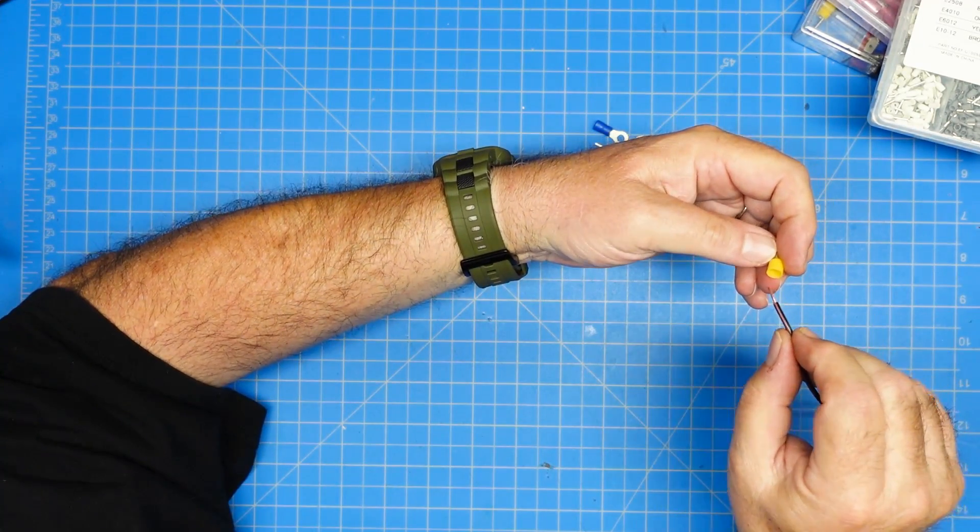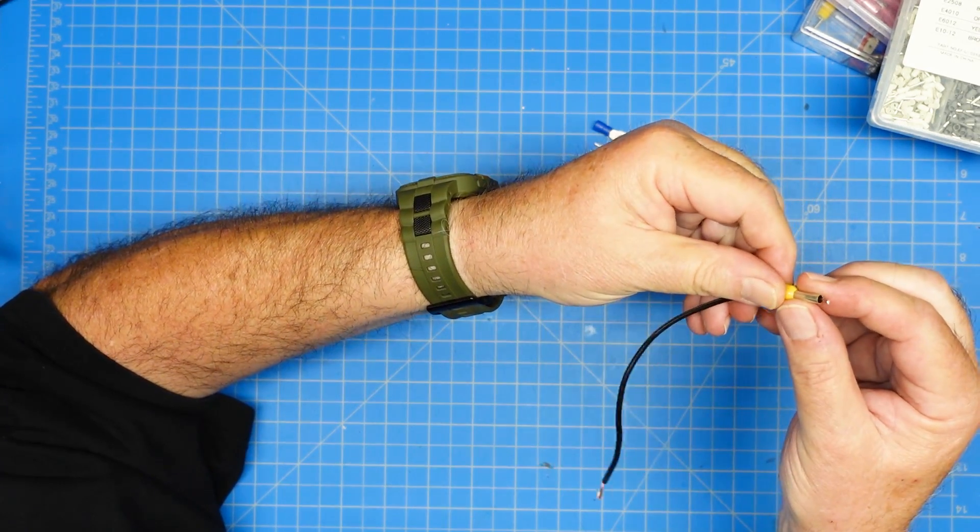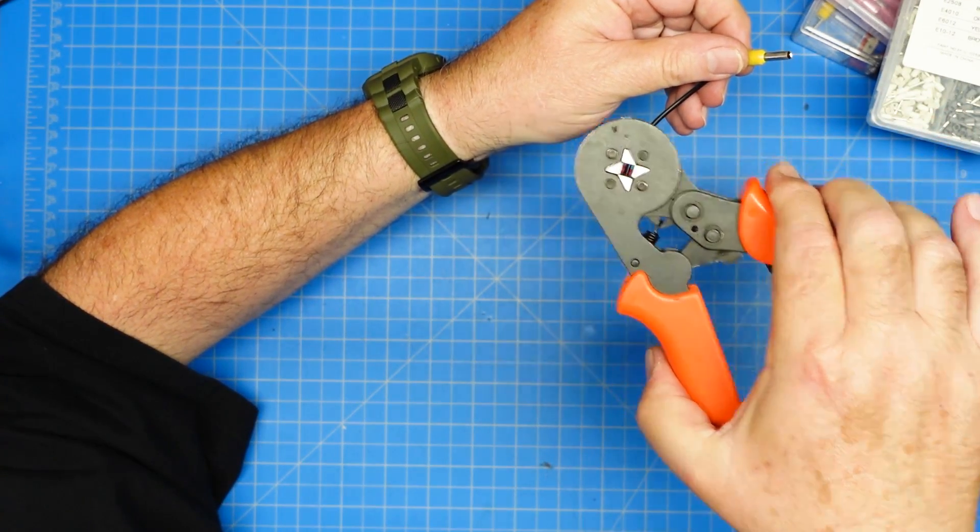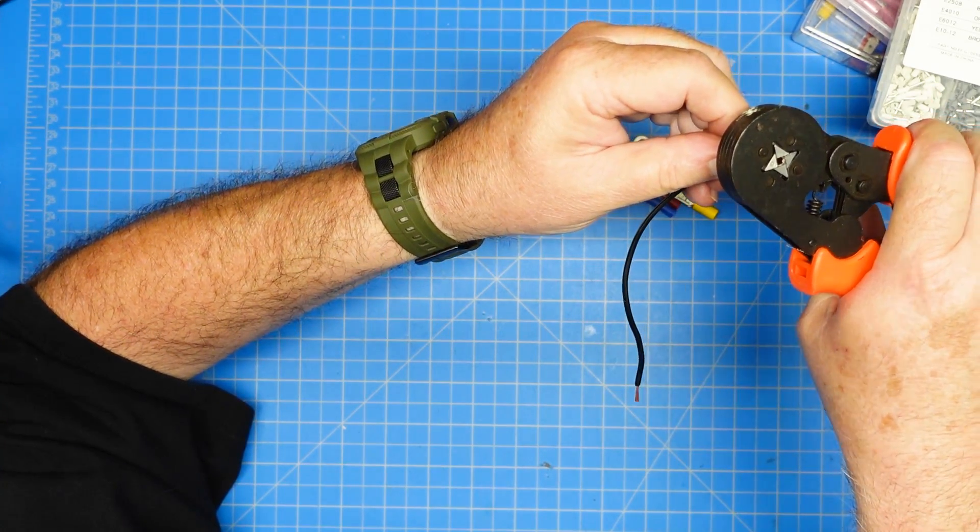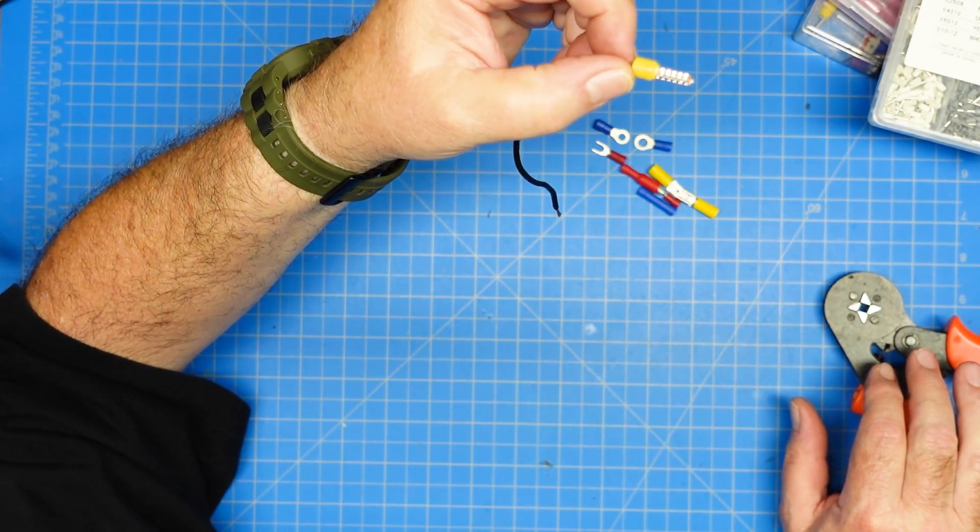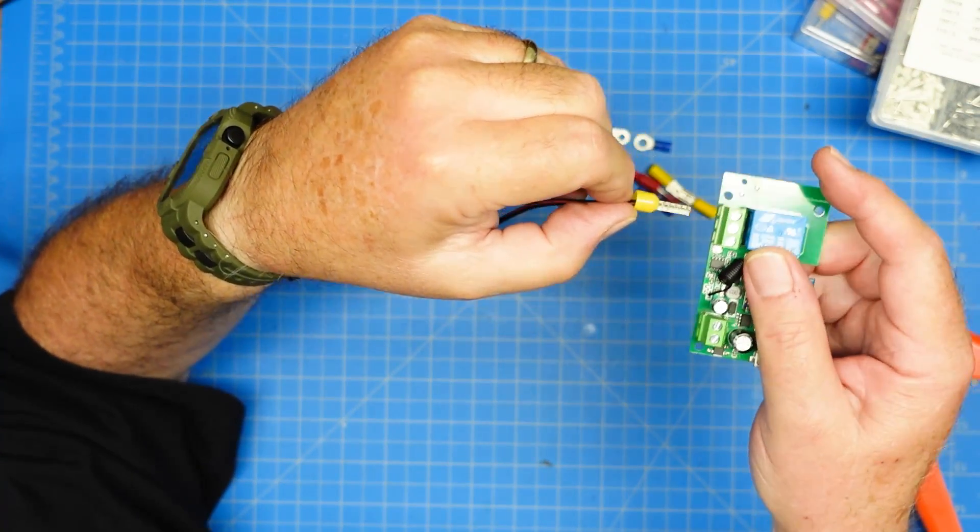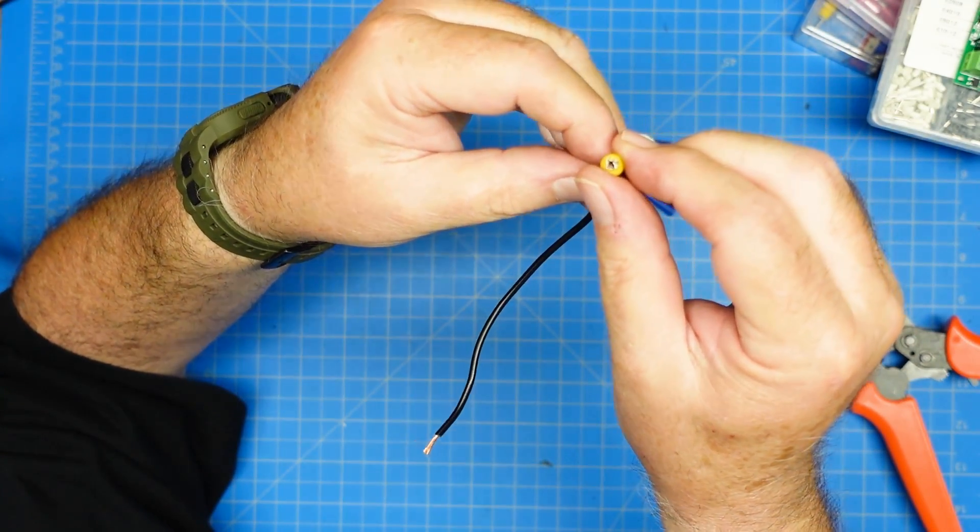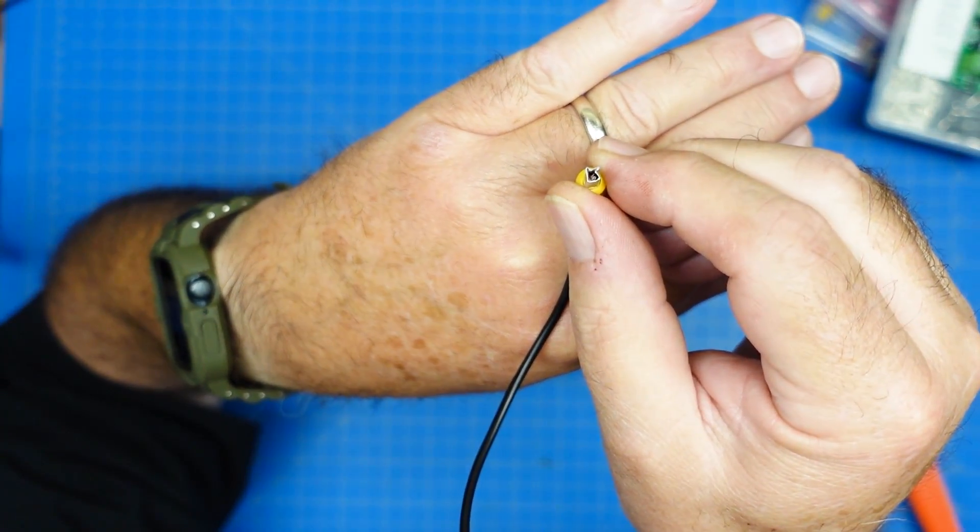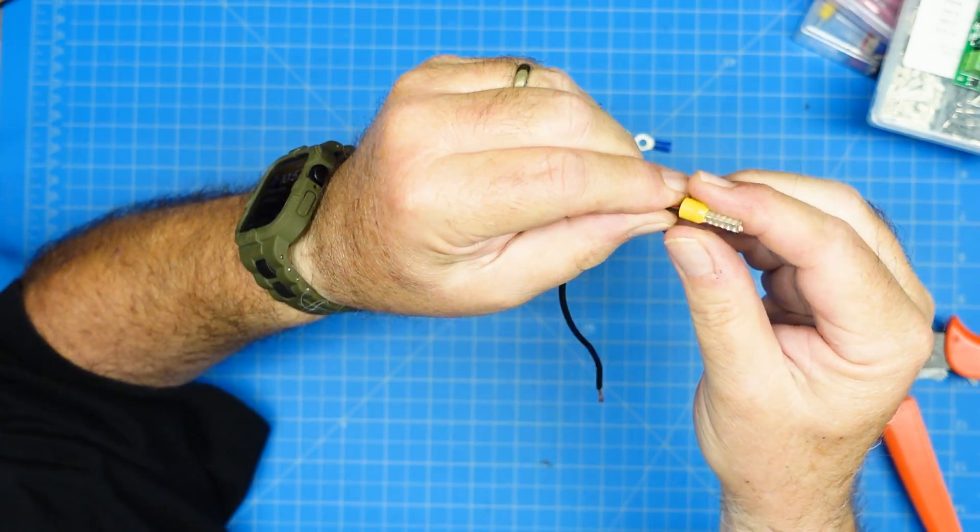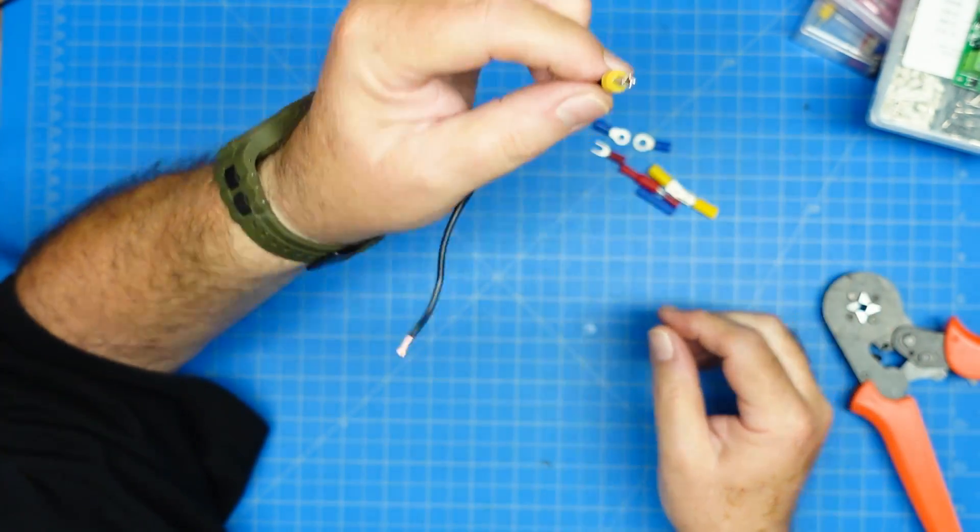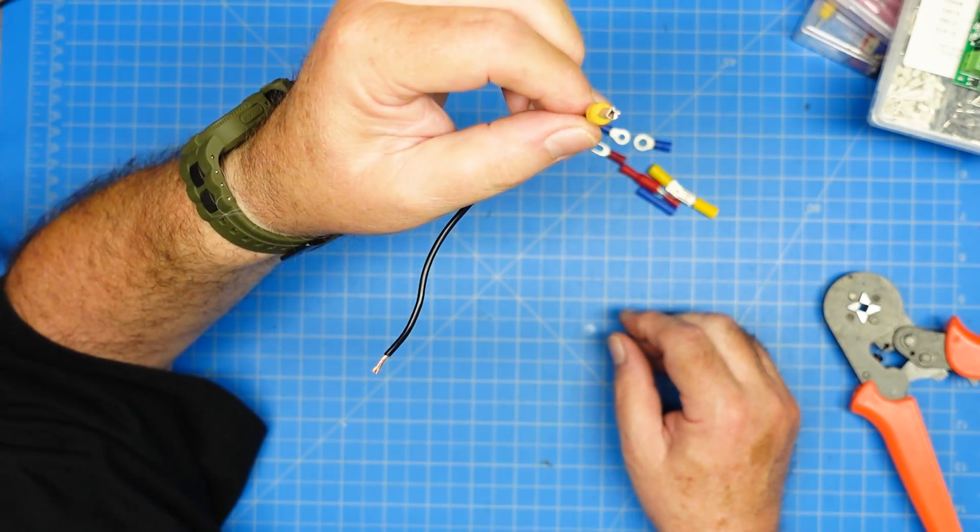And the way these work, similar to all the rest of them, is you put the wire up inside it, like so. And then you use the specialized crimper that I showed you earlier, and this is to crimp ferrules. And you come in here like this, and this is the wrong size wire for this ferrule. And you crimp it, and then you can see that it crimps it on four sides and gives you a nice square connection. And then that's designed to go, like I said, into these screw type terminals, and probably some other uses as well. That's what I use them for. Now, it's critical, and you can see here that this is a terrible connection, because you can see the wire floating around loose in there. So this probably, a bit a little better. I think some of that's because of insulation. But you really want the right size terminal. This wire is probably 16 gauge, and that's not designed for this big yellow connector. But that's what these are used for. So that's called a ferrule, F-E-R-R-U-L-E. You say it however you want, because I'm not entirely sure how to pronounce that.